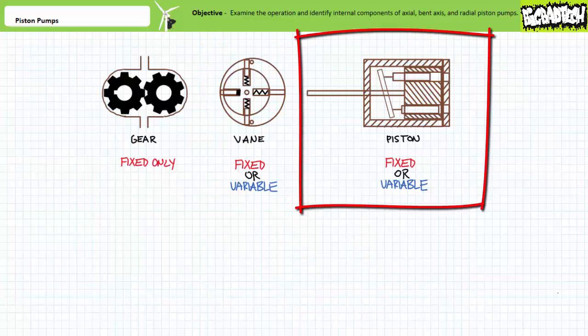A fixed displacement vane pump keeps the relationship between the rotor and cam ring constant, whereas a variable displacement vane pump varies the position of cam ring or rotor to vary displacement per revolution. Piston pumps could either be fixed or variable displacement pumps depending upon construction. A piston pump uses an angled plate to position pistons inside a rotating piston block.